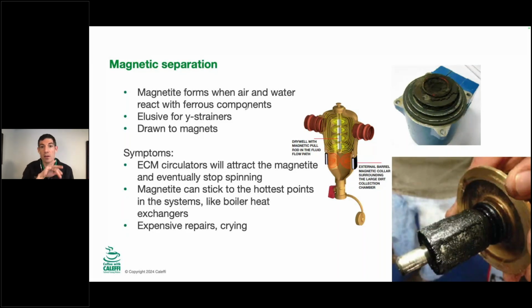Without the magnet there, it's going to blow through and find its way to another magnet, which unfortunately might be a really expensive part of your system. The rotor of an ECM circulator is magnetic, and it's going to catch all that magnetite if you don't catch it with a stronger magnet upstream. That's what we're doing there to protect that ECM technology, which is going to be the only option that we have very soon, which is great from an energy efficiency standpoint. We just have to protect them well.